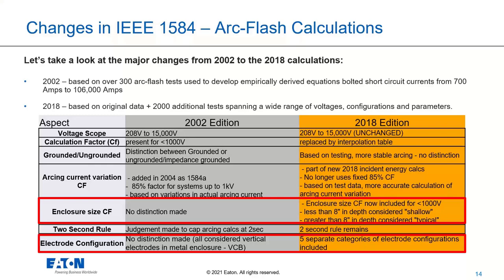And then the second one there is electrode configuration. What that means in terms of IEEE is really the layout of your three-phase bus work. How does that bus work move through that piece of equipment? In the transformer scenario, that bus work is really those spades, those terminals that are coming out of the secondary. That is our electrode configuration, versus maybe a piece of low voltage gear. Imagine you take the rear panels off and you might see horizontal bus and some vertical bus, and some goes in and some comes out of the gear, all sorts of different layouts. And depending on where that arc happens, it's going to propagate differently and you're going to get different resultant incident energy values. Very important to highlight those two pieces as we analyze these different setups and try to make the right choice for the product.